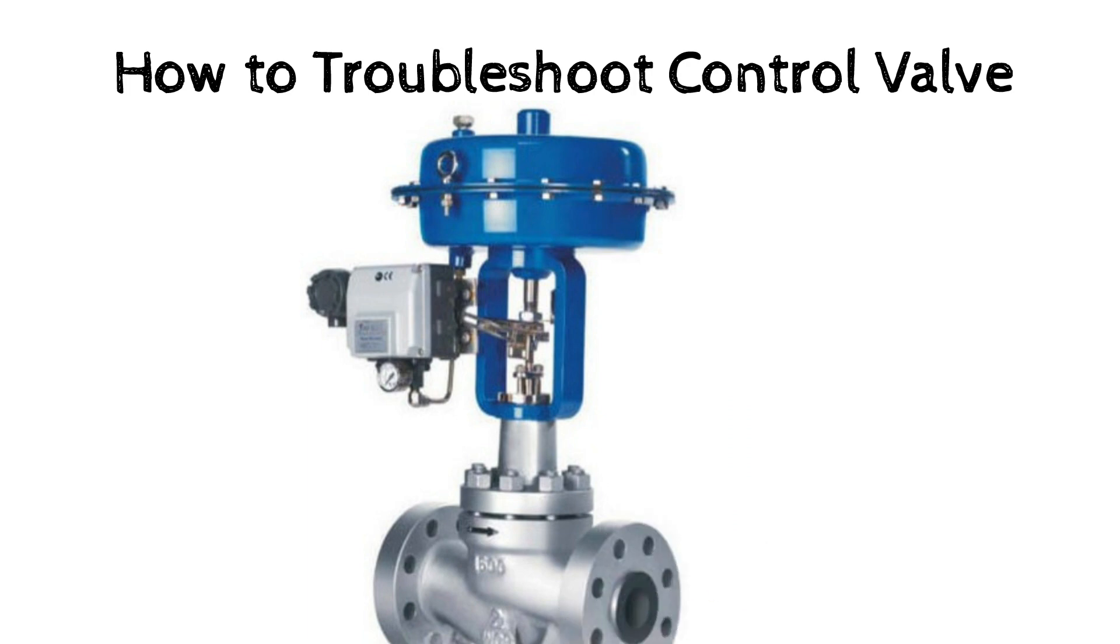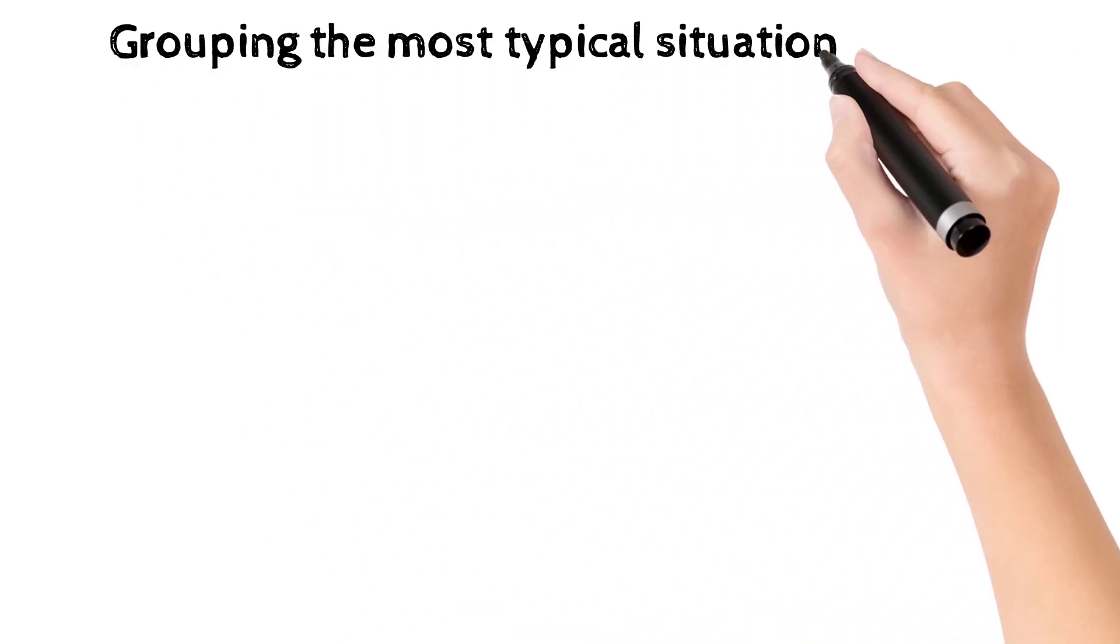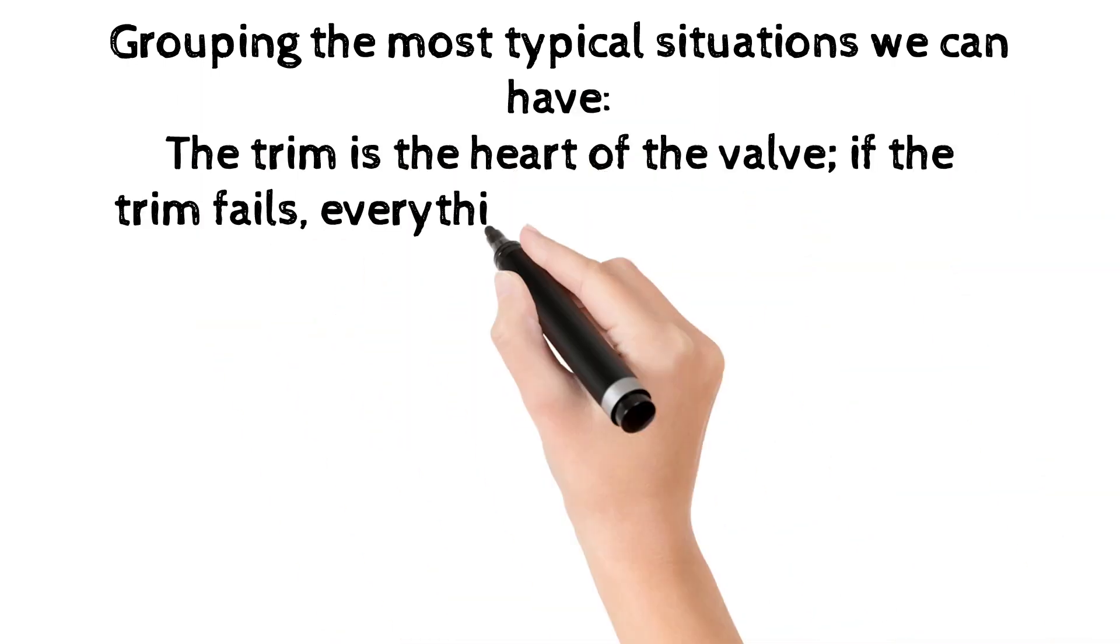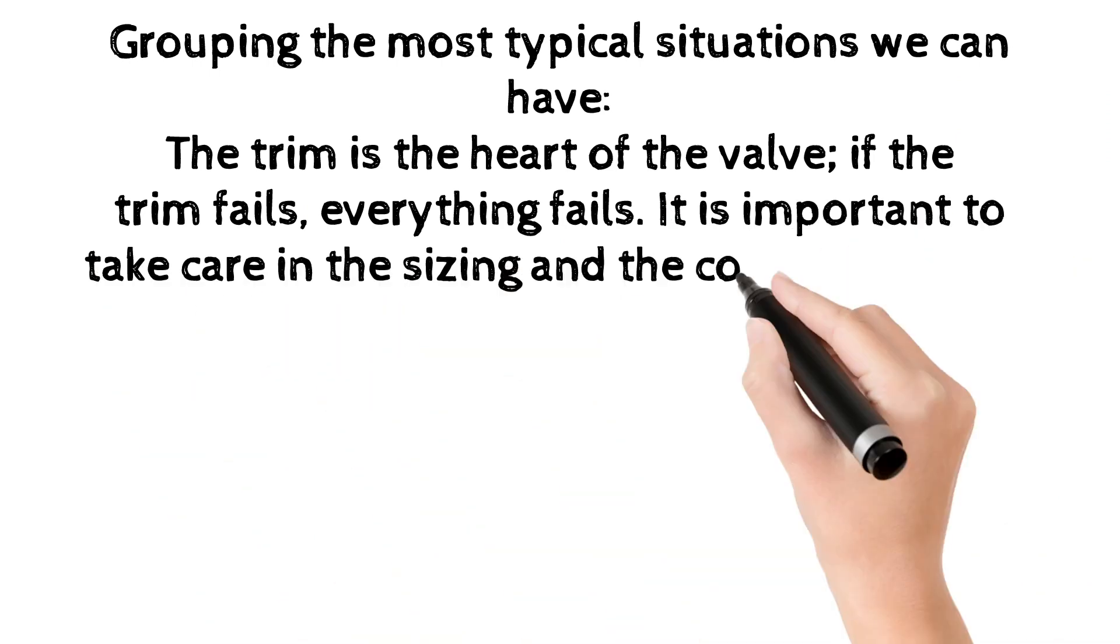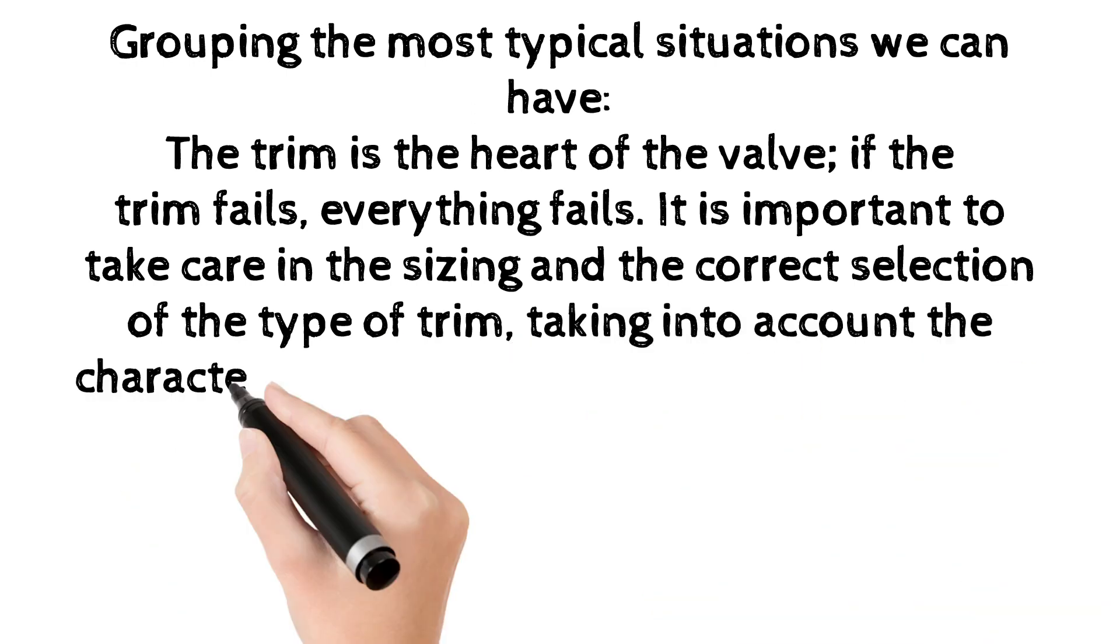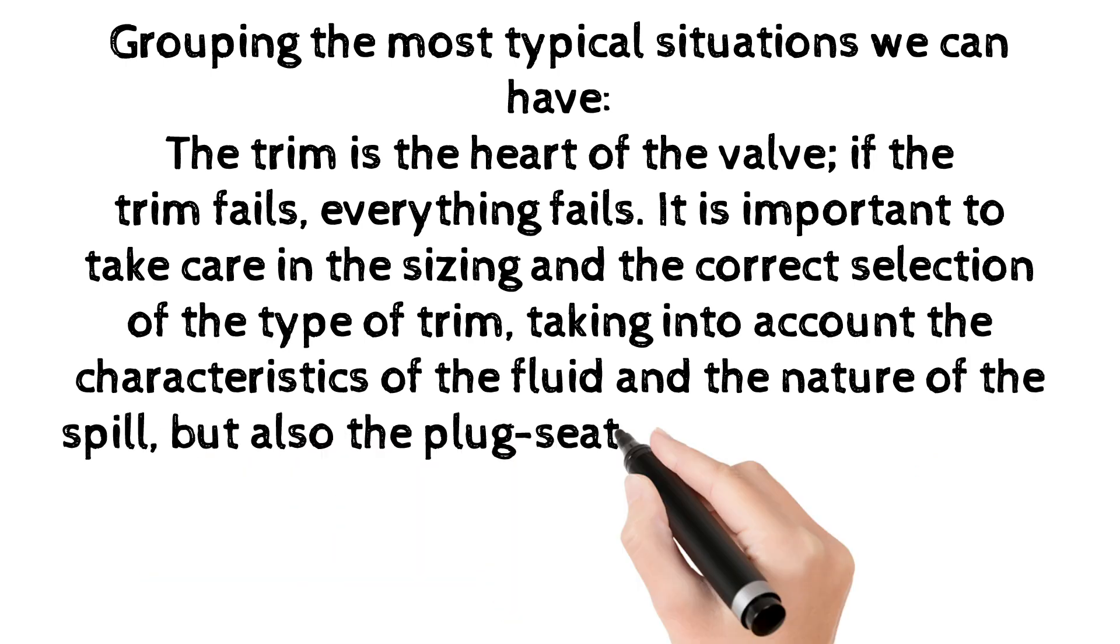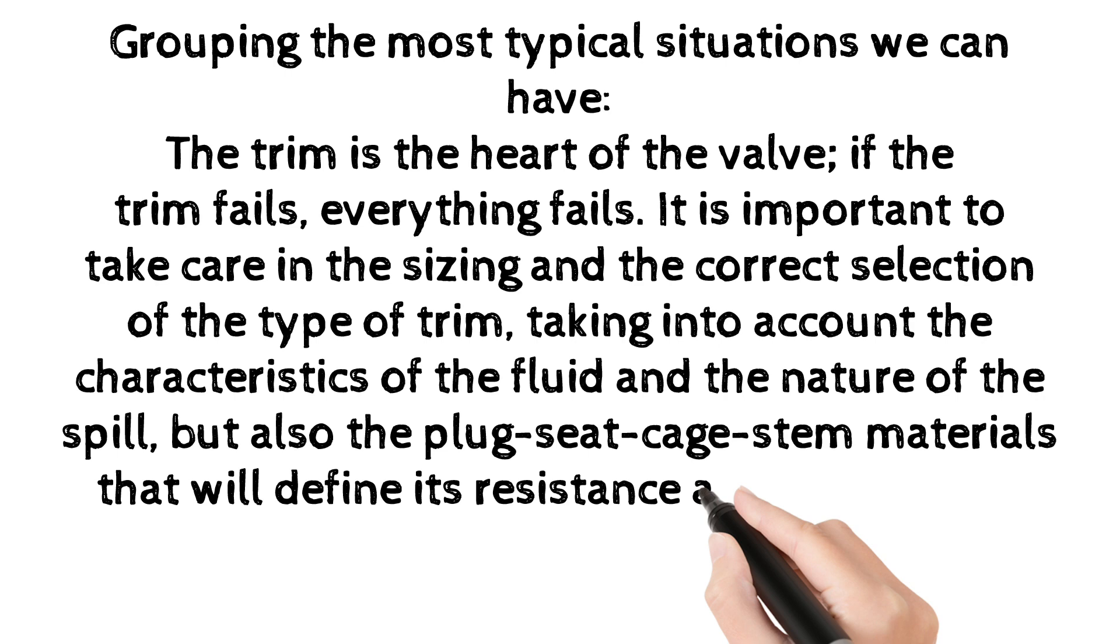How to troubleshoot control valve. Grouping the most typical situations we can have, the trim is the heart of the valve. If the trim fails, everything fails. It is important to take care in the sizing and the correct selection of the type of trim, taking into account the characteristics of the fluid and the nature of the spill, but also the plug-seat cage stem materials that will define its resistance and durability as the reliability of control over time.